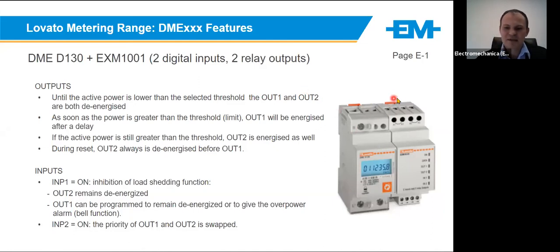the power's on the meter, the input is triggered. On that input, now it says, okay, now I'm on generator, and based on a rule, now I disconnect loads. So you could maybe disconnect the air conditioning system because it may not be seen as essential while I'm on generator. So there are a couple of combinations or sequences you could do.